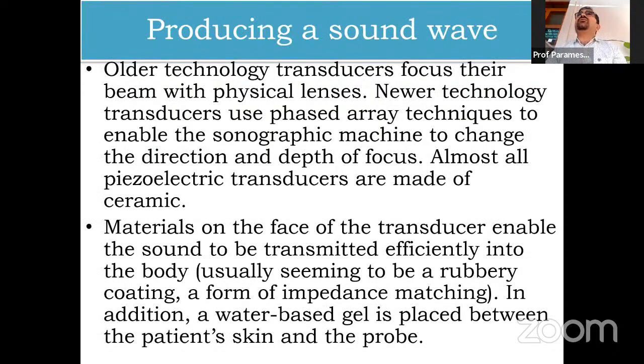Next. Producing a sound wave: this is the older technology. Transducers used to focus their beam with physical lenses, but after the invention of ultrasound, better quality transducers have come, and they use the phased array technique to enable the sonographic machine to change the direction and depth of the focus. Almost all these piezoelectric transducers are made of ceramic. Materials on the face of the transducers enable the sound to be transmitted efficiently into the body using a rubbery coating, a form of impedance matching. In addition, a water-based gel is placed between the patient's skin and the probe for easy movement of the transducers over the body. Next.